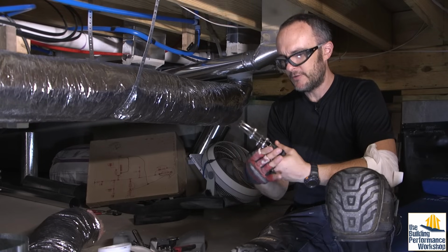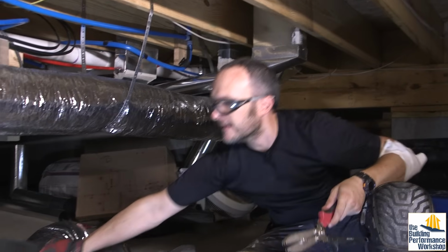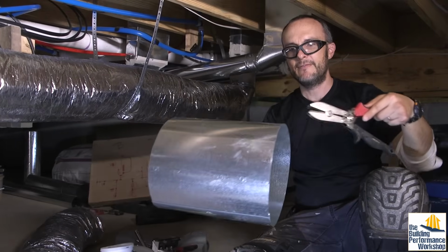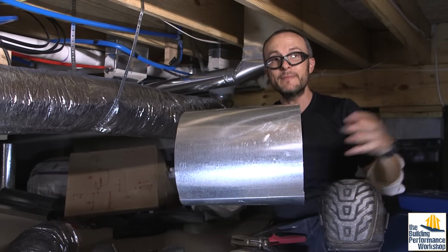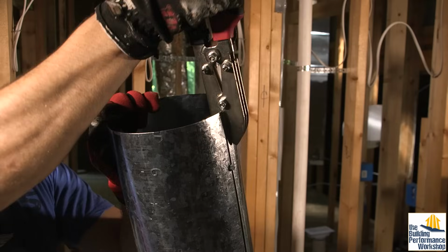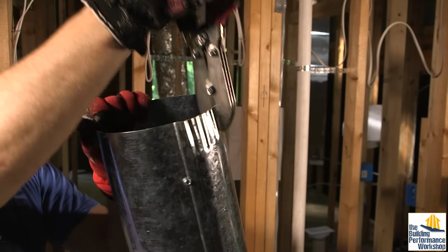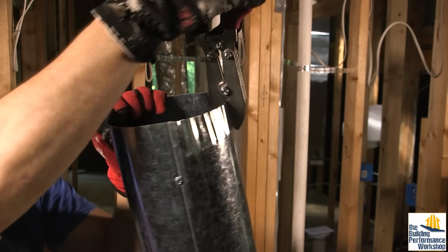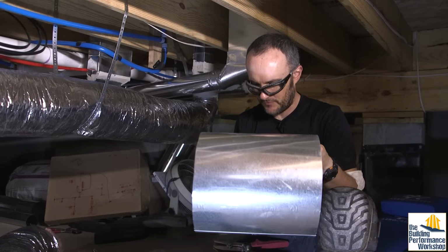Crimpers are really useful and very important, because every single cut you make, where you make something like this, now I have a straight end on both of these, and that means I have to have a crimped end on both sides, which doesn't make sense, because generally you're going to crimp one side, then the next piece you're going to crimp that side, so that the air is always going in. It's kind of like flashing on the outside.